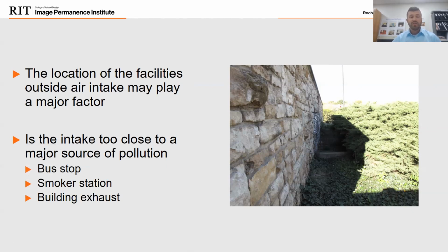What exhaust would we be bringing directly in? As a former facility manager, in the building that I used to manage, the outside air that was brought into that facility was right outside of the smokers area. So someone at some point in time thought, we're going to bring in the outside air and put the smokers there. And you can imagine the complaints that were happening anytime someone stepped outside for a cigarette. So keep in mind, where could that be located? Some sources of major potential pollution that can be near you: factories, airports, major traffic, fires if they're occurring, storms, or like I said, smokers or even fireworks could cause some issues. Any questions? Okay.